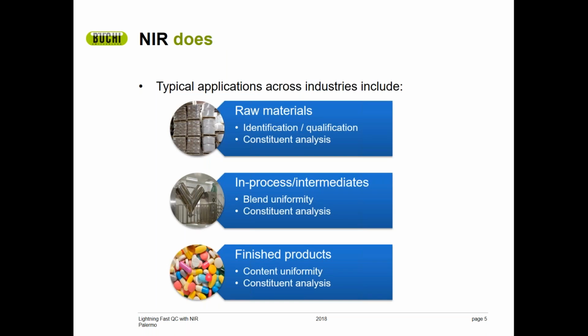Here is an overview of NIR applications within the pharmaceutical and other industries. NIR is most widely used for raw material identification and 100% label inspection. There are also quantitative applications that apply to raw material receiving, including compositional analysis like moisture, protein, or fat content. In-process or intermediate analysis is also possible. Typical examples include things like blend uniformity or determining percent moisture in a drying operation. Finished product testing using NIR can be accomplished on powders, liquids, or compacted solids. Examples also exist of identity or counterfeit testing on finished products.